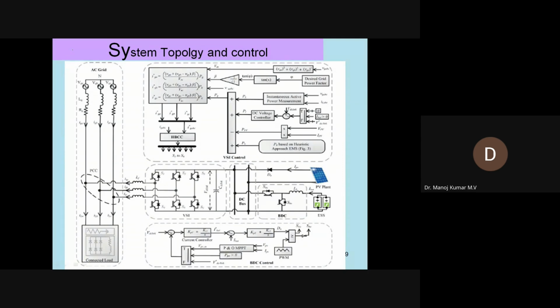But the point is, in this controller, there is also flexibility to control the amount of reactive power taken from the grid to supply the load. So basically, the control structure will be able to control the reactive power, which means it actually controls the power factor of the individual load, not the total load connected here. In another way, the power factor associated with the grid current and grid voltage can be exactly controlled. It may not always be at unity power factor, it can be controlled.